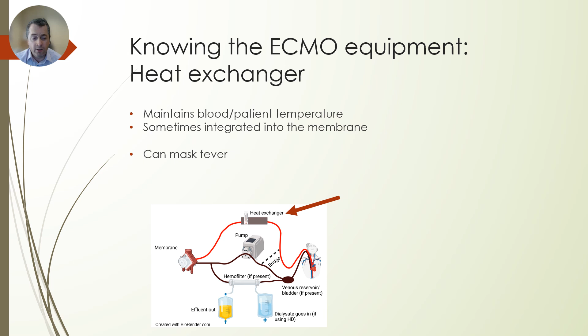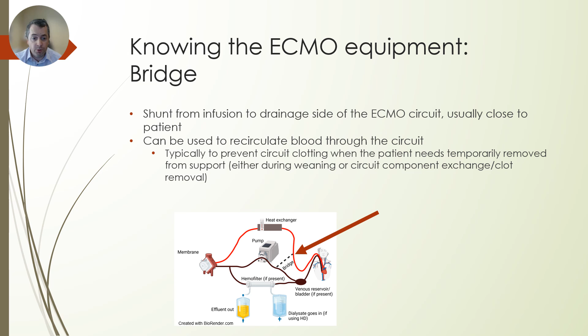Another optional component, the bridge, is a shunt from the infusion to the drainage side of the ECMO circuit, usually close to the patient. It can be used to recirculate blood through the circuit without pausing flow, which prevents circuit clotting. This is used when the patient is either being weaned from ECMO support or when a component needs to be exchanged or clots removed.